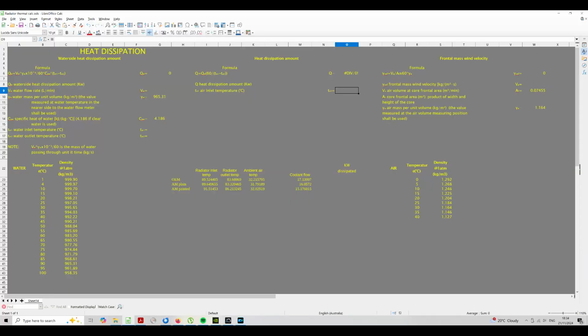With all the data recorded, I'll go over some of the parameters I had to conform to in order to meet the JIS standard. One was the water inlet temperature - the temperature of the water flowing into the radiator shall be regulated to maintain the inlet air-to-water temperature difference at 60 degrees Celsius, plus or minus 10 degrees Celsius, in the state of heat dissipation.